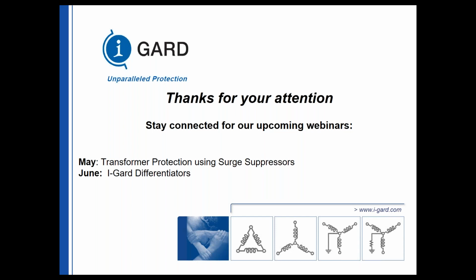Thank you. The next one is, is there a means to easily disconnect the i-Gard i-AVT if the circuit being isolated needs to be tested, for instance, via megger or insulation resistance? No. I was going to say you can pull the fuses out, but you said easily, and removing the fuses does not disconnect the device from the bus. So no, there is no easy way of isolating the i-Gard i-AVT from the circuit if you want to do a megger test.